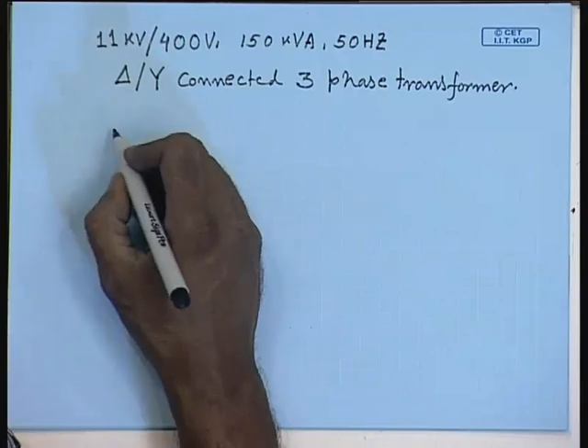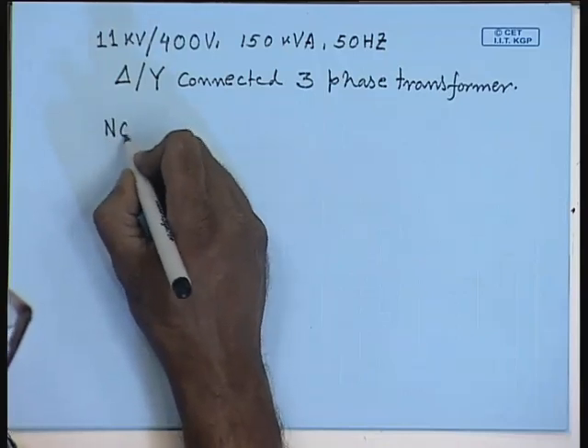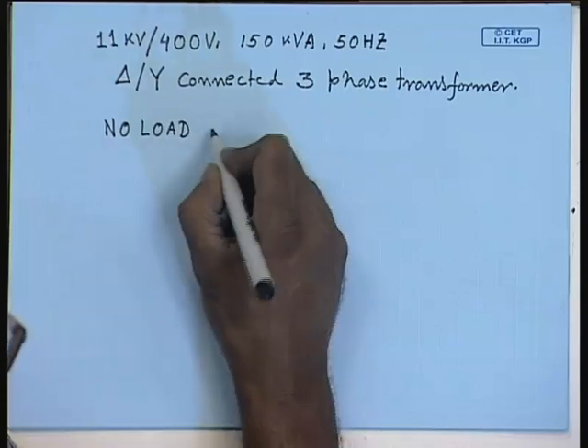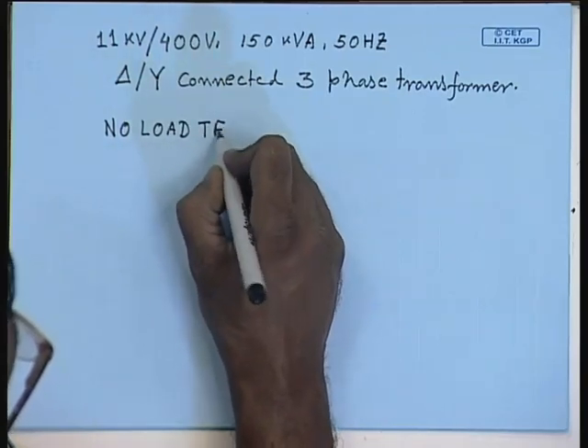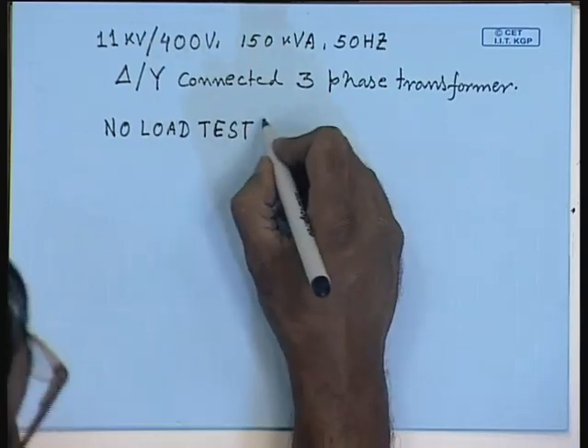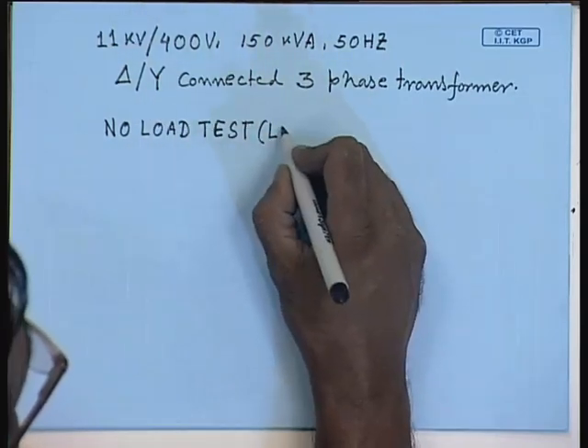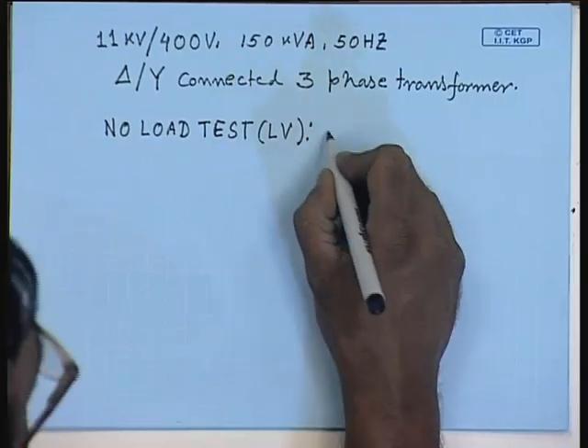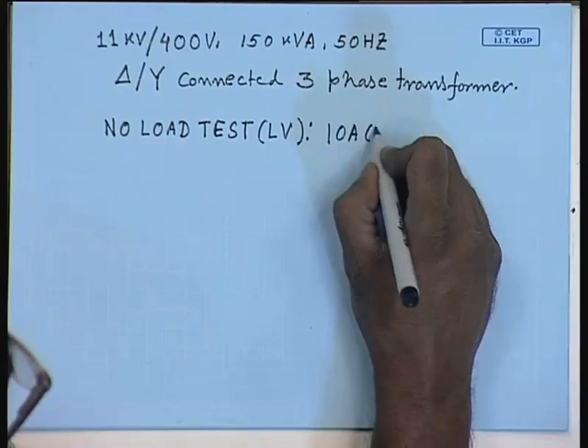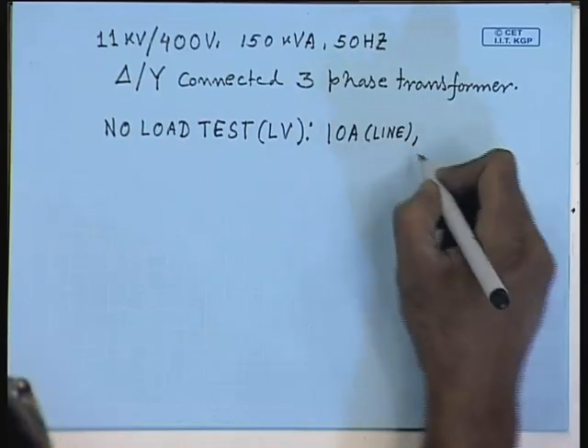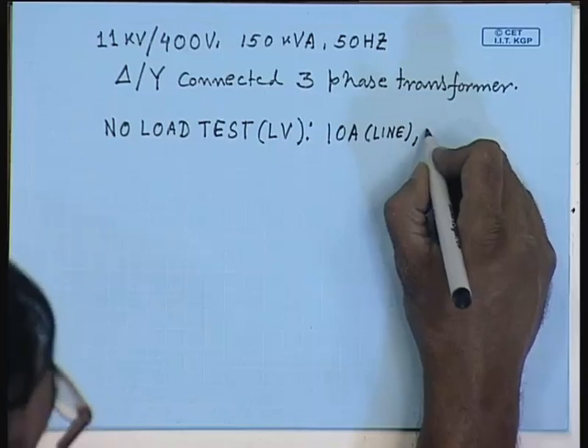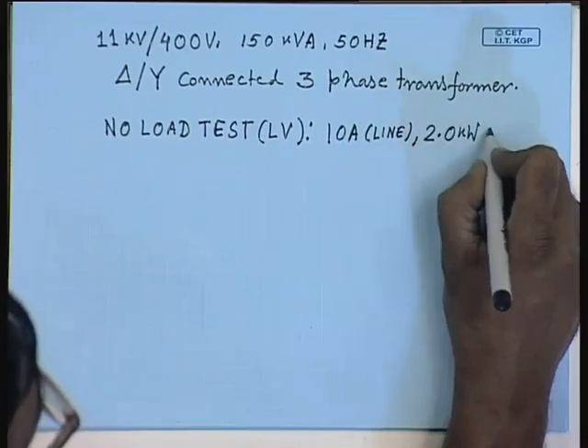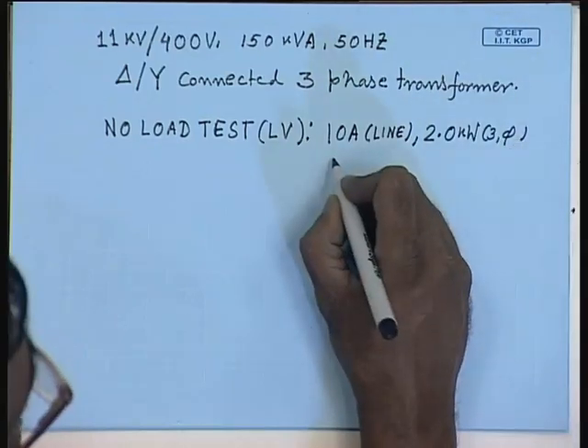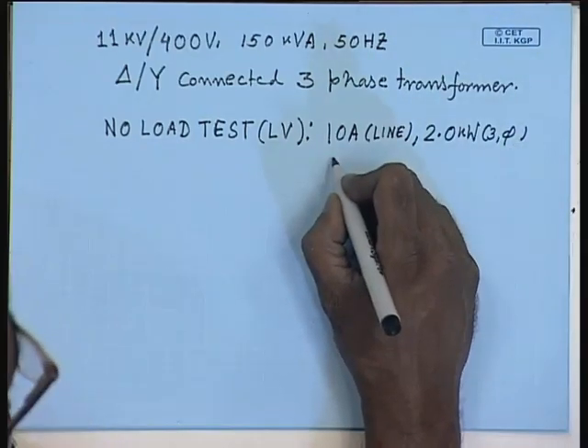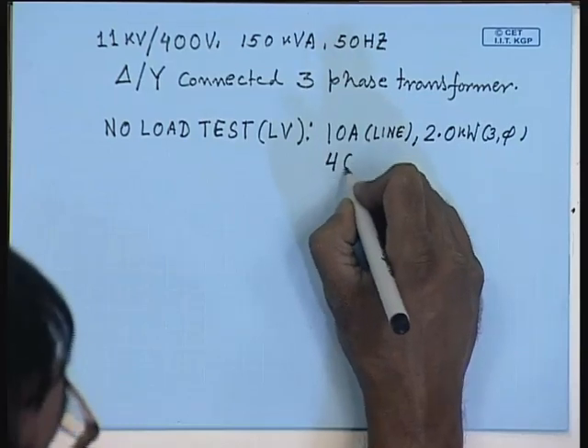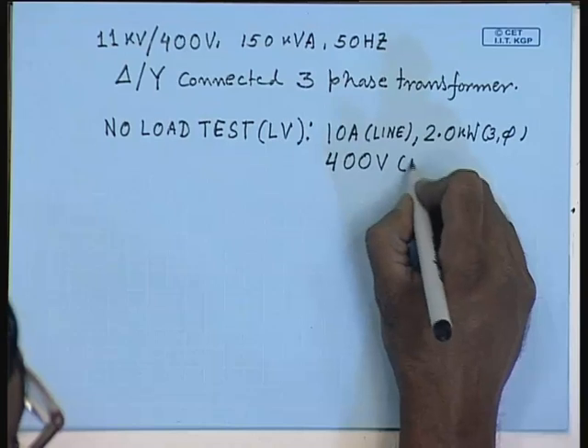From the no load test, no load test data, which was done on the LV side, that is on the Y connected side, is as follows. The line current is 10 ampere and the 3-phase power is 2 kilowatt, when rated applied line to line voltage is given. The line to line voltage is rated line to line voltage 400 volt.